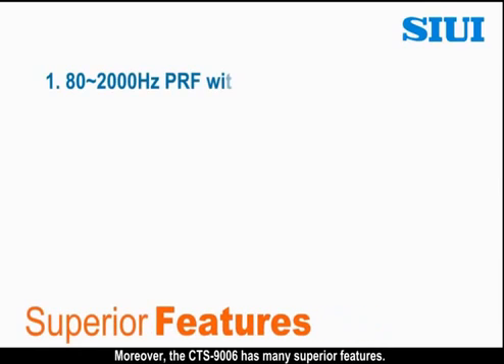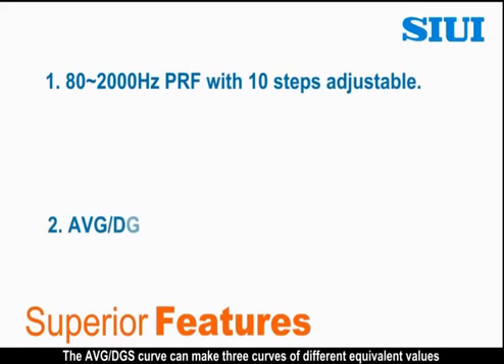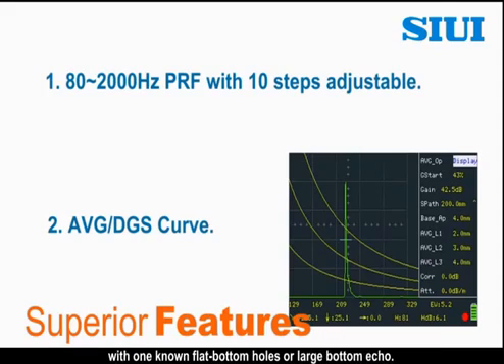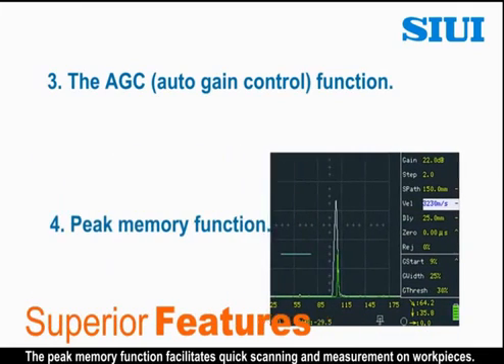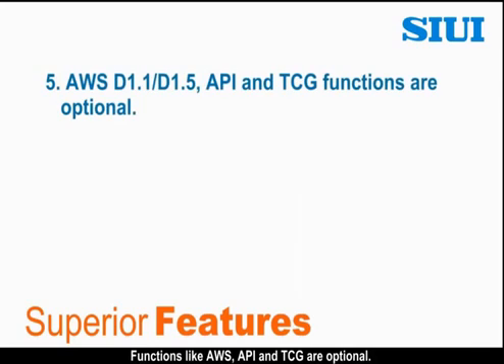Moreover, the CTS-9006 has many superior features. It has 80–2000 Hz PRF with 10 steps adjustable. It can avoid reverberation signals during detection. The AVG-DGS curve can make three curves of different equivalent values with one known flat bottom holes or large bottom echo. The AGC function with peak echo and image freeze function can help you quickly identify the highest echo. Functions like AWS, API and TCG are optional.